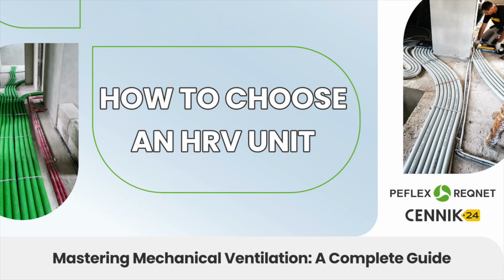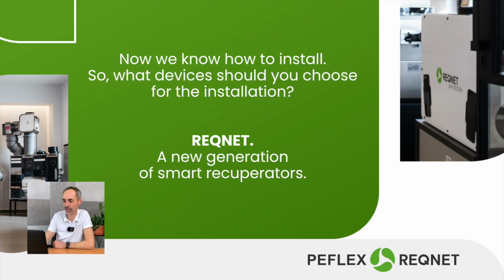So, we already know how to install the system, and now we should choose the right device for it, meaning the heat recovery unit. Remember, at one point during the air balance discussion, I mentioned that we would also need a second value, that second value regarding the resistance of the system, or the resistance that the installation creates, so that the heat recovery unit is able to overcome all of that resistance in the system. So, we need to select the ventilation unit based on two parameters, capacity and the resistance of the system, that is, according to the available pressure.